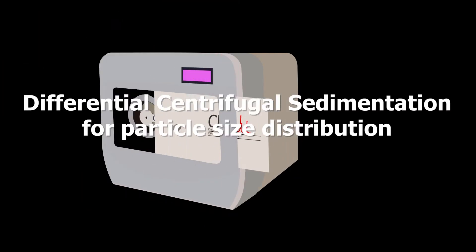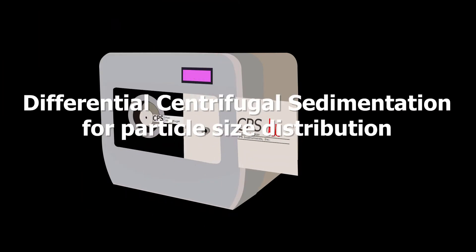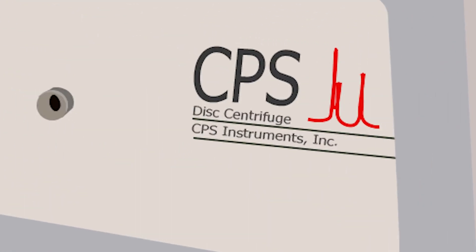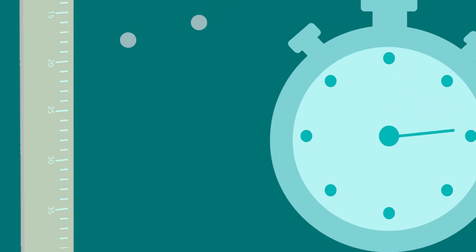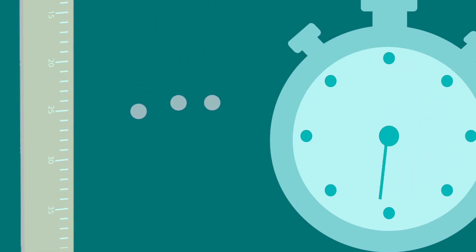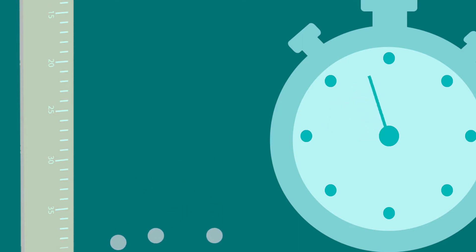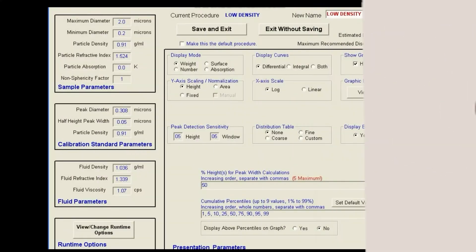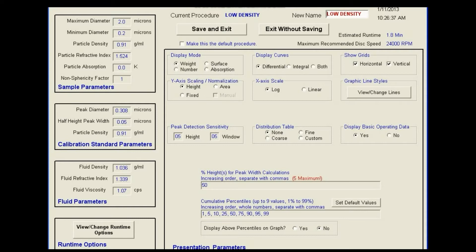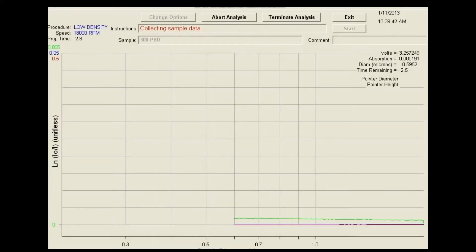DCS can be used to analyze particle size distribution. The technique utilizes a modified version of Stokes' law to determine an unknown distribution of particle sizes by measuring the time it takes for the particles to settle from a known distance in a liquid of known viscosity and density. Exposure to high g-force through a centrifuge allows the sedimentation of even very small particles — down to just a few nanometers in size — to occur quickly, enabling real-time analysis.